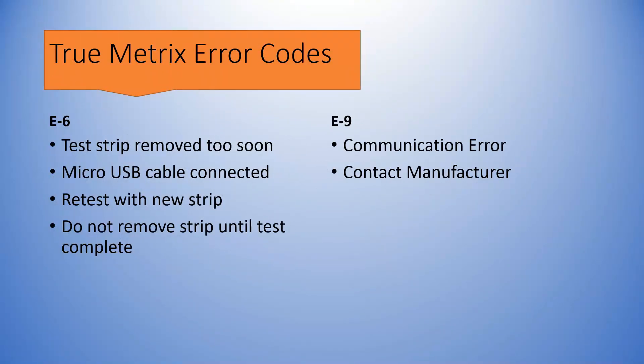E6 means the test strip was removed too soon, so simply retest with a new test strip and ensure the test strip is left in place until the meter has completed the test. The micro USB cable could also be plugged into the side of the meter, in which case it won't test properly — remove the cable and repeat the test.